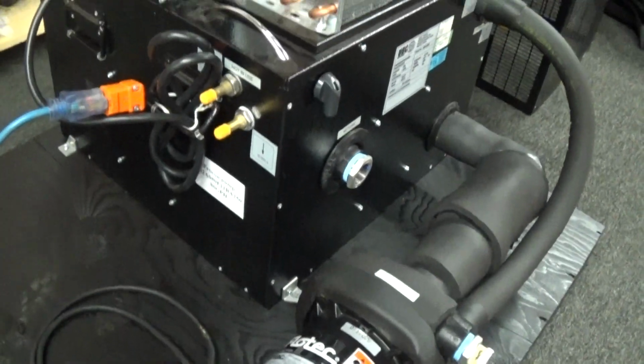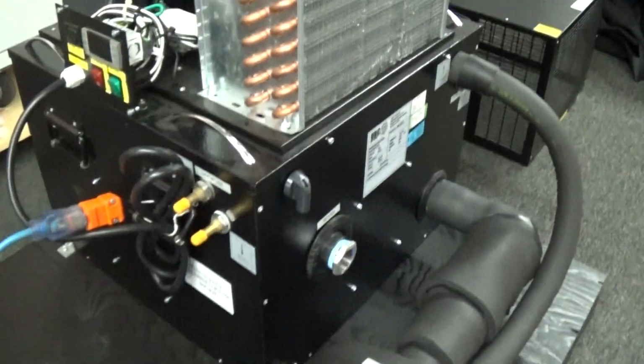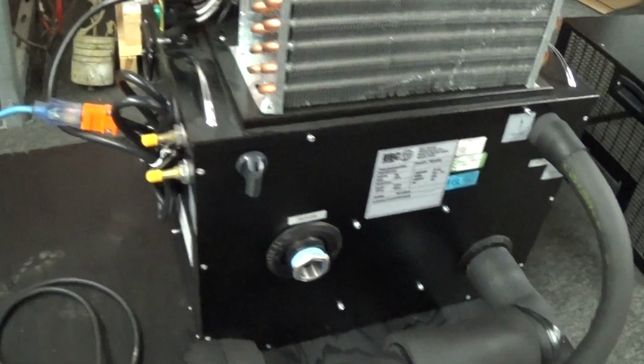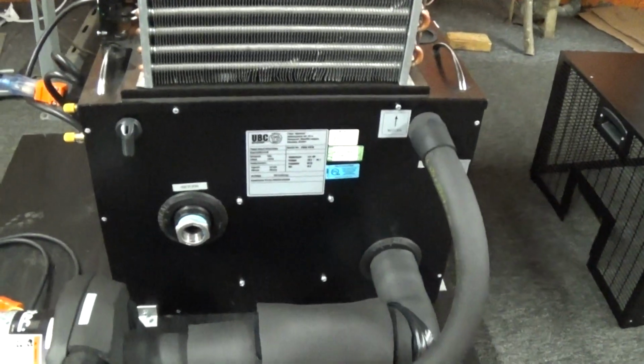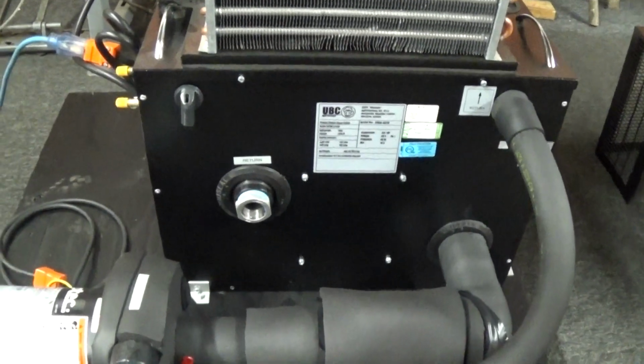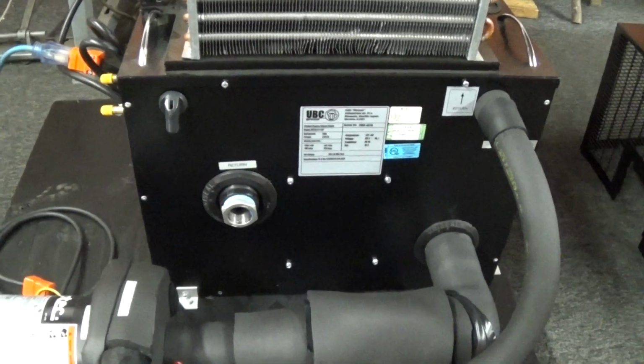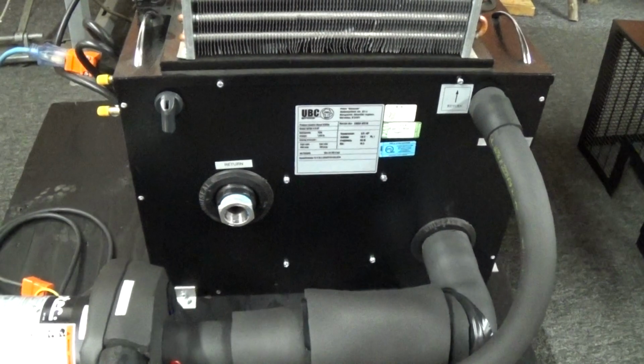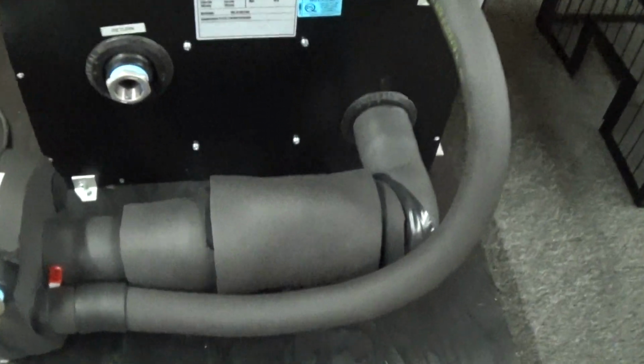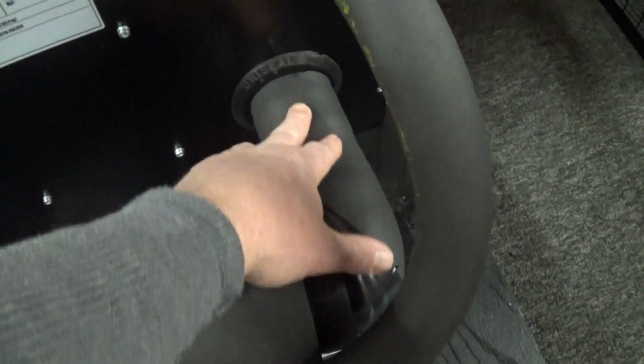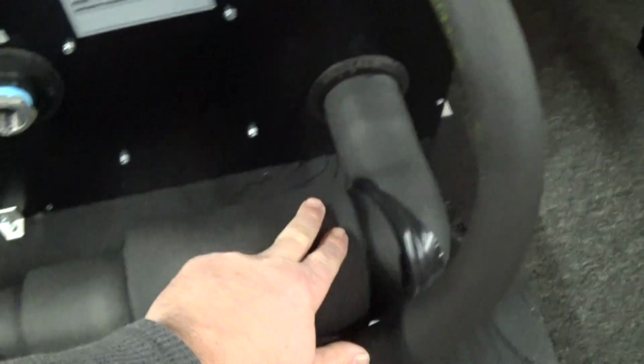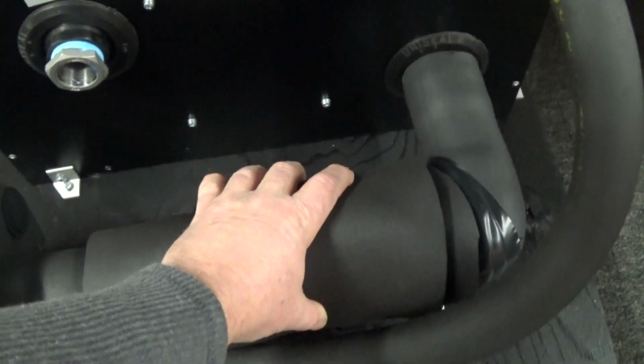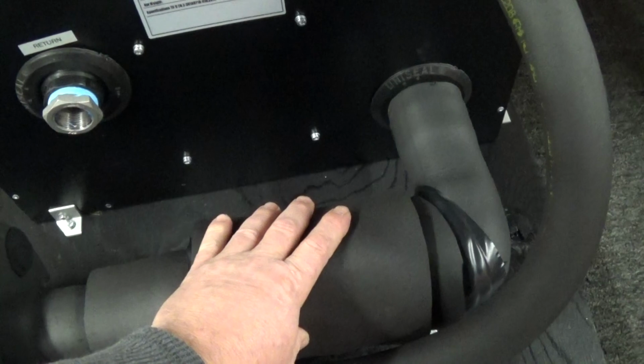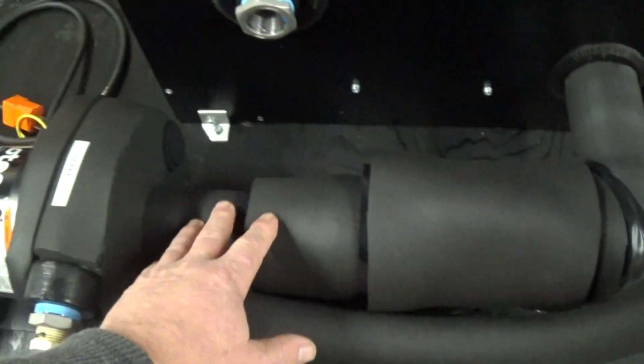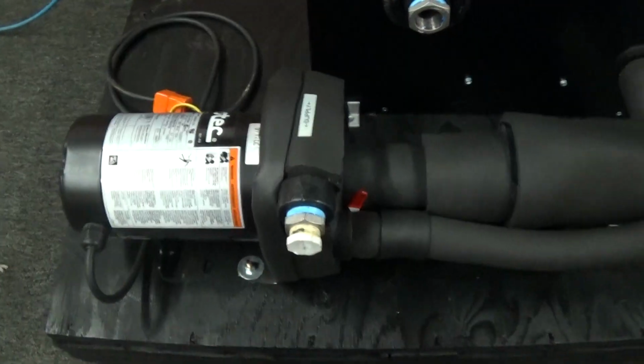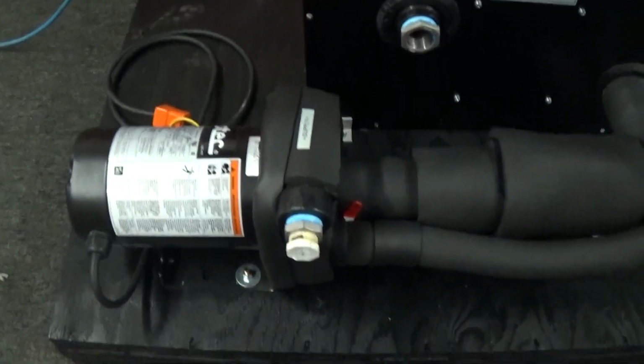portion. So what we have done on this unit is we have put in our own fittings intentionally to service several 3.5 barrel or 5 barrel fermenter and brite tanks. So we have the insulated line, which draws from the reservoir here. There's actually a shut-off here. You don't need to worry about that now. It's just for maintenance. That goes into the suction side of this 1/2 horsepower Glycol pump.